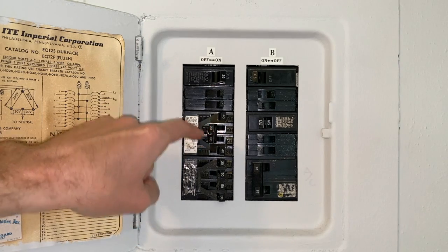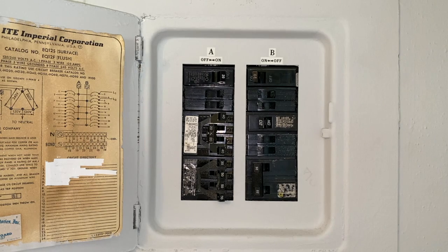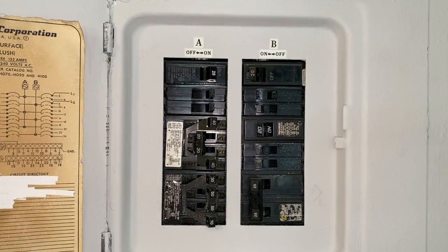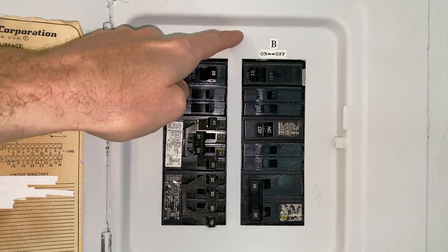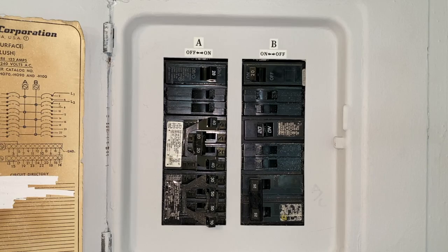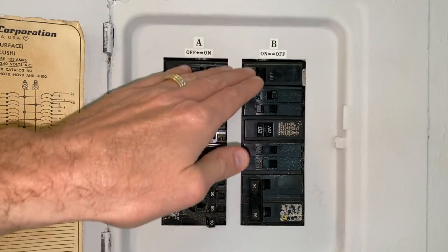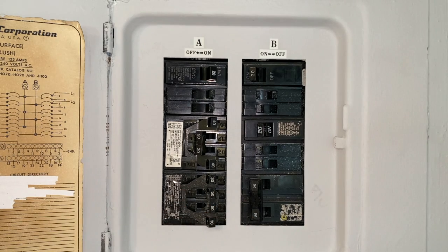As you can see, in the center portion of this 4-breaker setup, we have two 20 amp poles built into the same breaker, and they do not come apart. Again, coming up top, there is no main shutoff breaker. In most cases, you'll have either one main, which is really big, or two mains, one for each side or respective bus, that you can carefully trip or turn to the off position to cut all electrical power feeding down to your entire circuit breaker panel and all of your breakers. However, we don't have that, and we will show you what we want to do next.